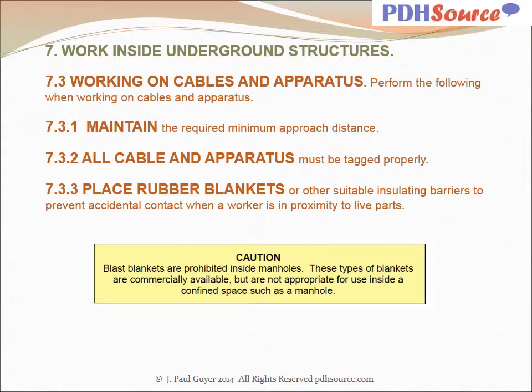Perform the following when working on cables and apparatus inside underground structures. Maintain the required minimum approach distance. All cable and apparatus must be tagged properly. Place rubber mat blankets or other suitable insulating barriers to prevent accidental contact when a worker is in proximity to live parts. Caution: blast blankets are prohibited inside manholes. These types of blankets are commercially available but are not appropriate for use inside a confined space such as a manhole.